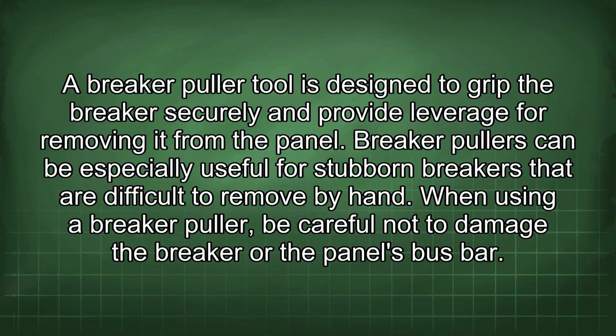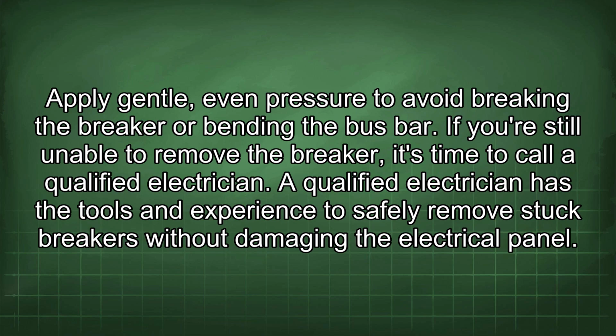When using a breaker puller, be careful not to damage the breaker or the panel's bus bar. Apply gentle, even pressure to avoid breaking the breaker or bending the bus bar. If you're still unable to remove the breaker, it's time to call a qualified electrician.